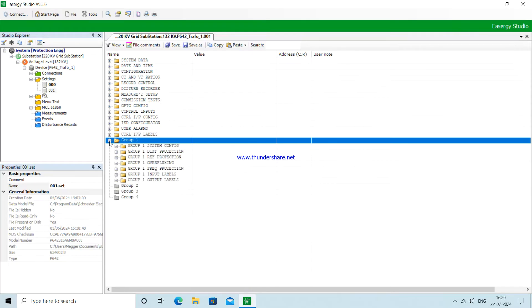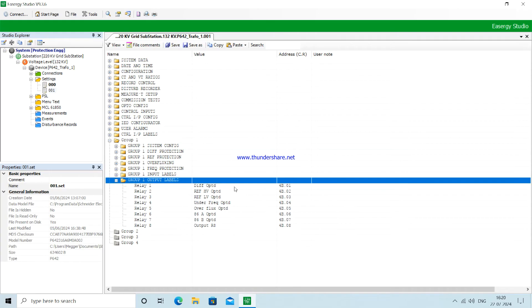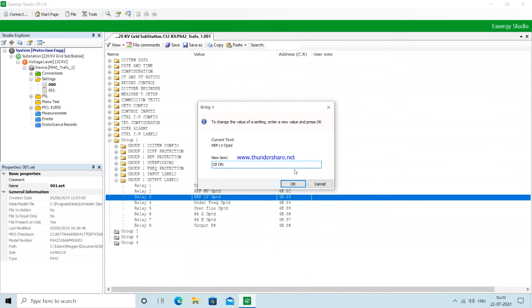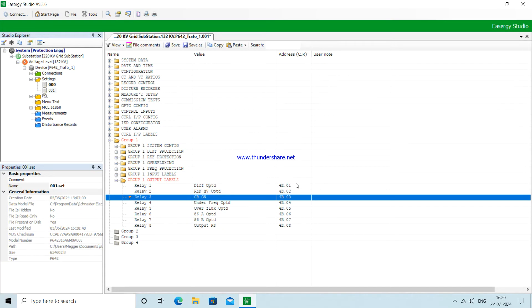We need to move on to relay output configuration. We have to configure relay output two and relay output three, which will be used for breaker control. We will use relay output three for CB on and relay output two for CB off. These outputs will actually give the actuating commands to the circuit breakers.